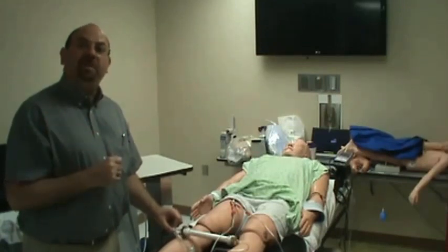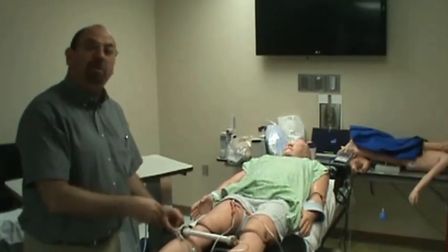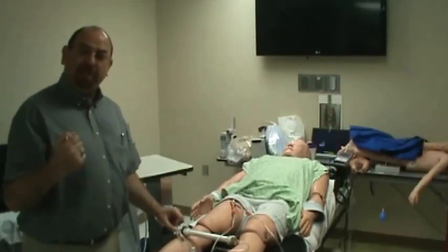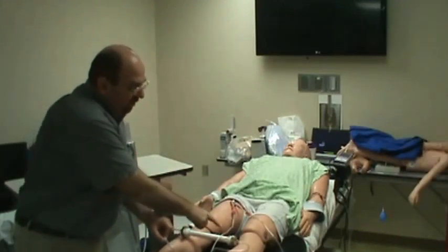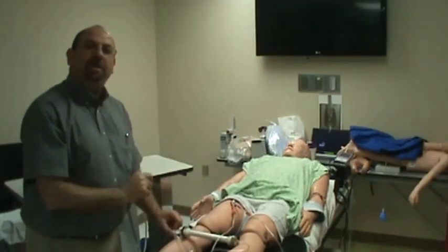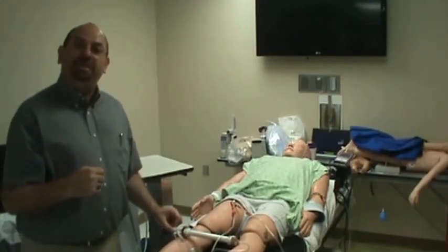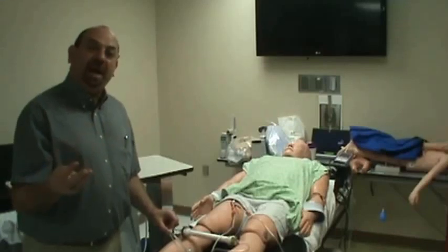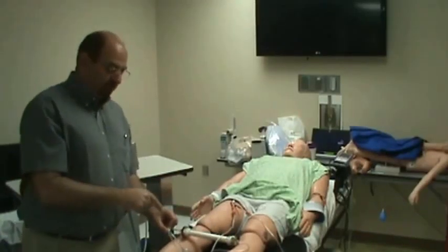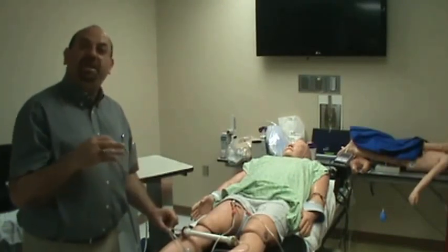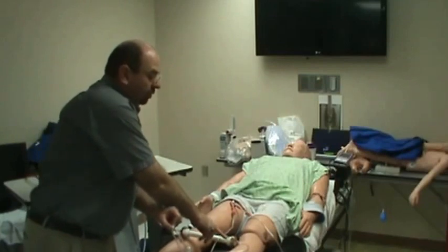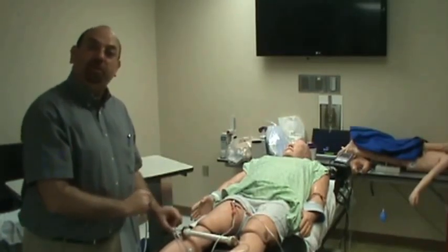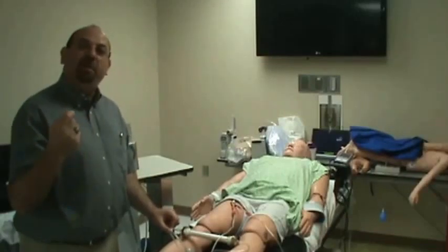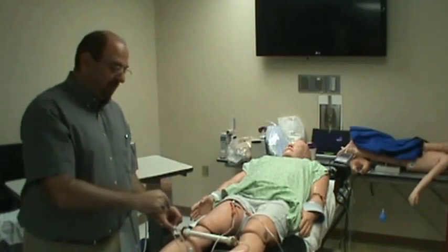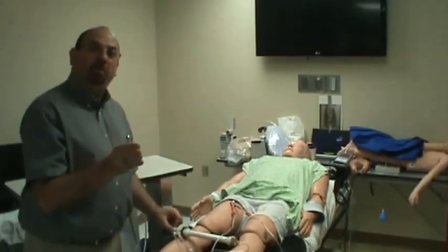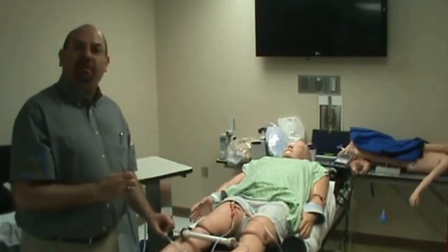Or you can actually infuse dianeal, which is peritoneal dialysis fluid, right in that port, as considered a replacement fluid. Now think, if you're having 700 coming out of here and you're putting 500 in here, you may be effectively having 200 cc's of urine output per hour. If the patient is dehydrated, 500 coming out of here, you replace here with 700. If the patient is massively volume overloaded, 700 come out of here, you replace with 300. So in a way, you have the ability to control the negative fluid balance by adjusting the replacement fluid rate and comparing that to the rate of ultrafiltration that's coming out of the filter.